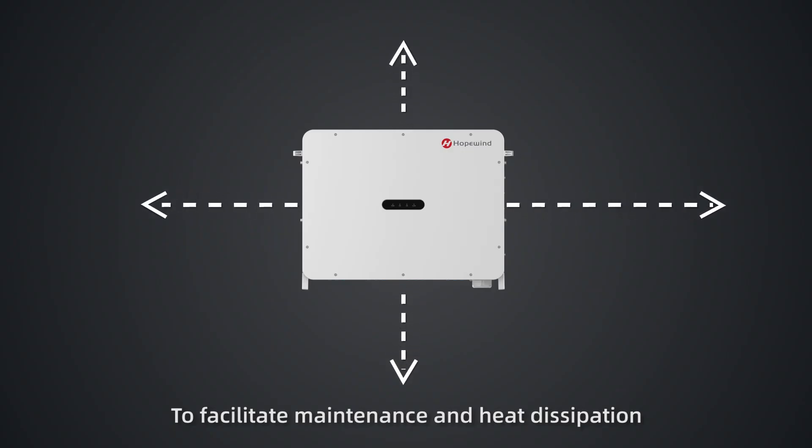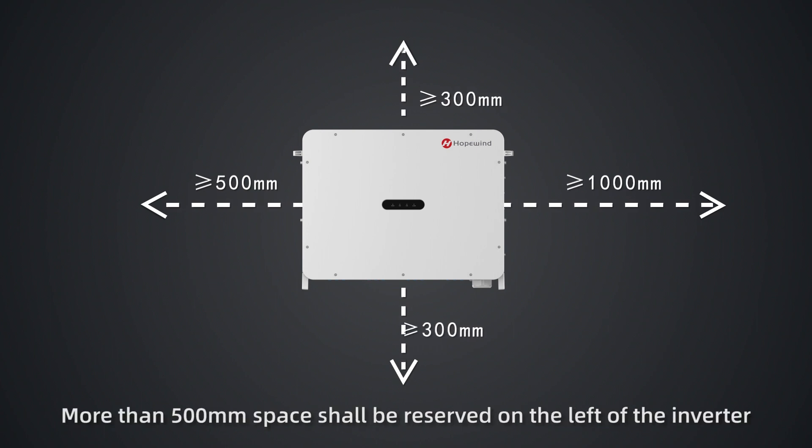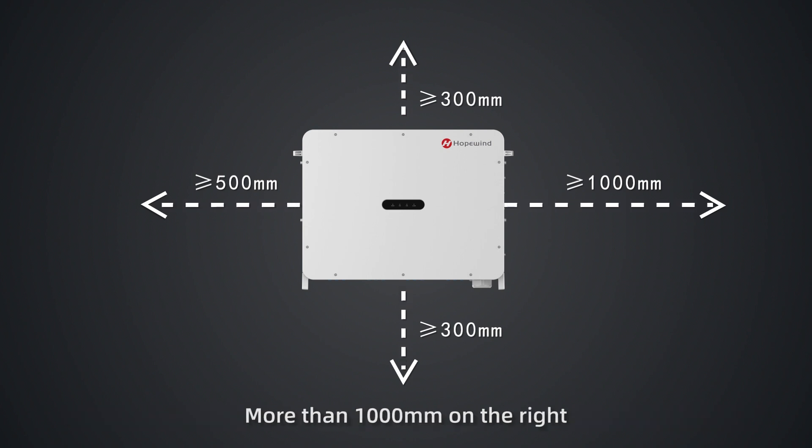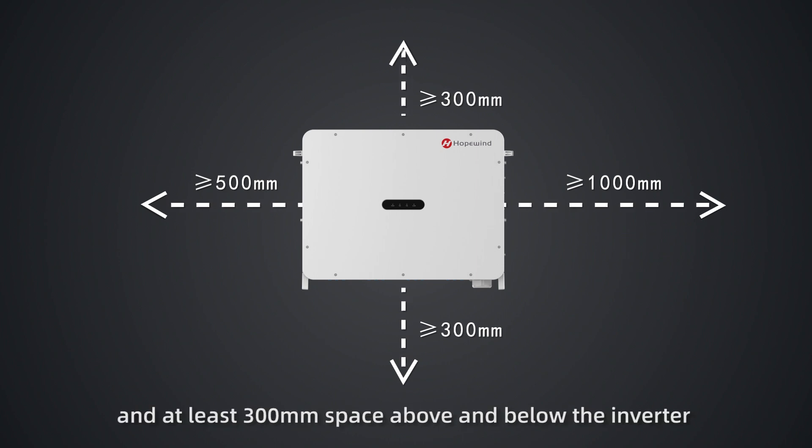To facilitate maintenance and heat dissipation, more than 500mm space shall be reserved on the left of the inverter, more than 1000mm on the right, more than 300mm on the back, and at least 300mm space above and below the inverter.